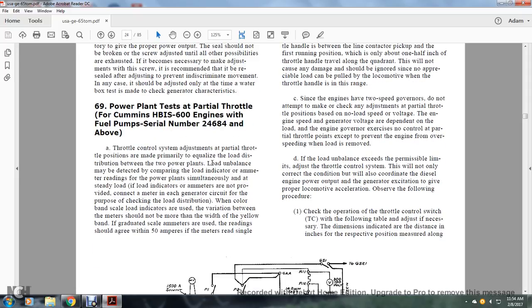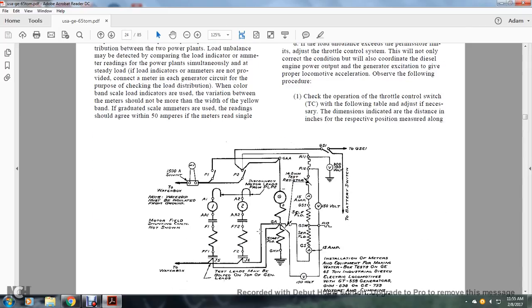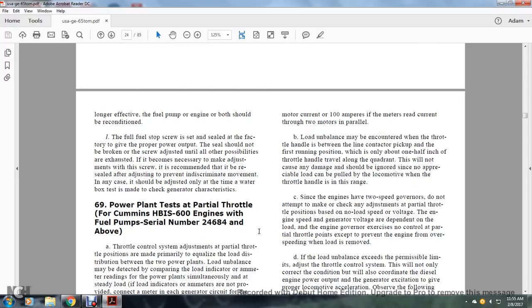Section 69, Power Plant Testing — Partial Throttle, for the Cummins HBIS 600 engine, fuel pump serial number 24684 and above. The throttle control adjustment at partial throttle positions is made primarily to equalize load distribution between the two power plants. Load imbalance may be detected by comparing the load indicated by the ammeter readings for each power plant simultaneously under steady load. The variation between meters should not exceed the width of one band on the graduated scale, or the ammeters used should agree within 50 amperes. A motoring current of 100 amperes is for the meter reading the current for the two motors in parallel.